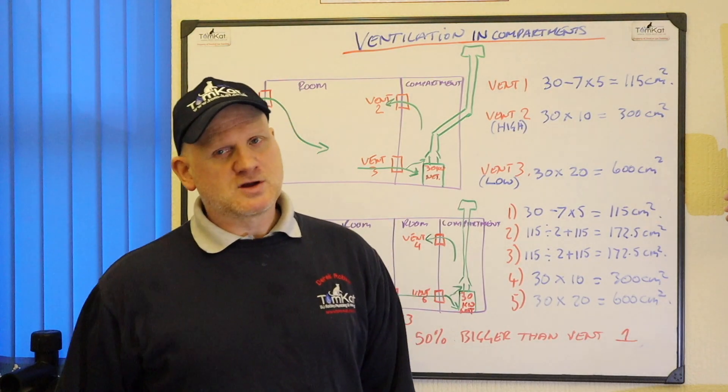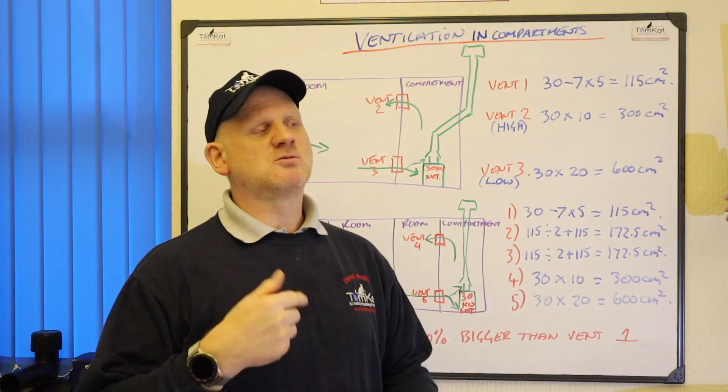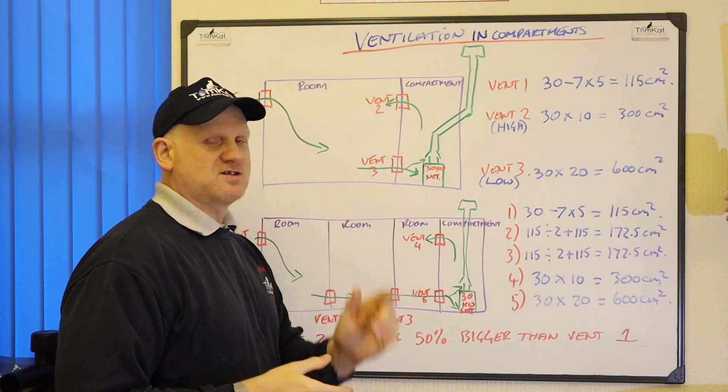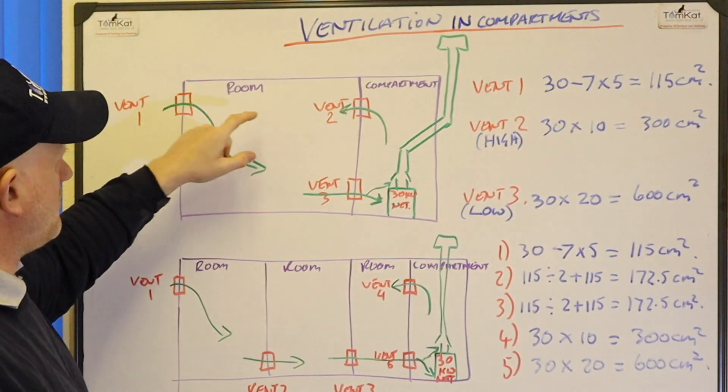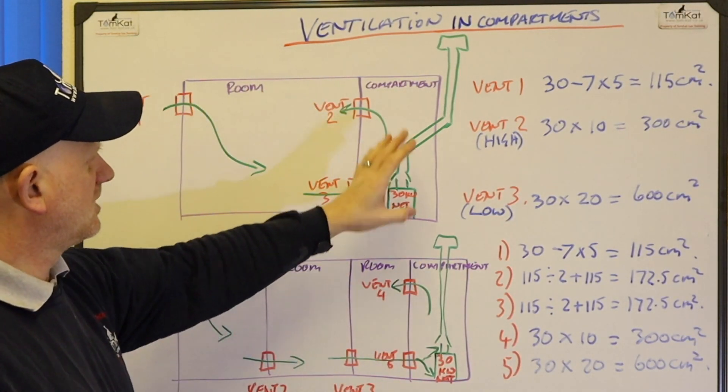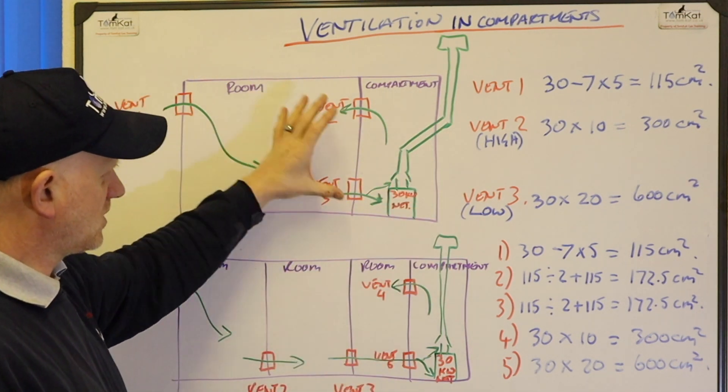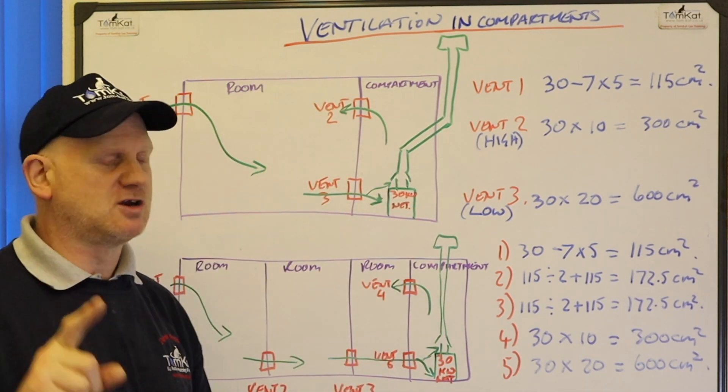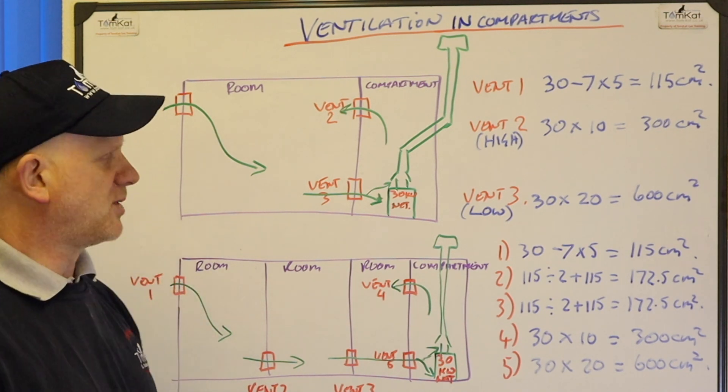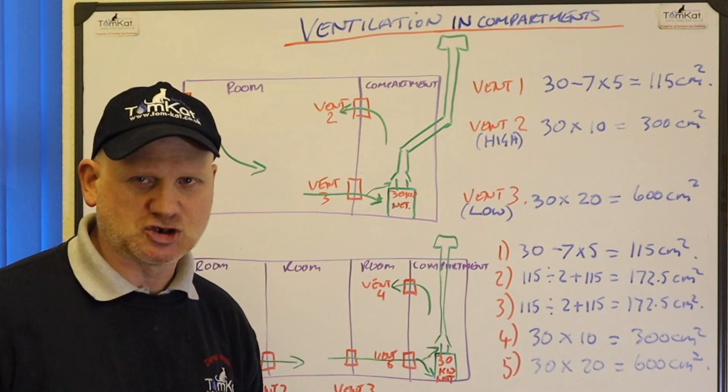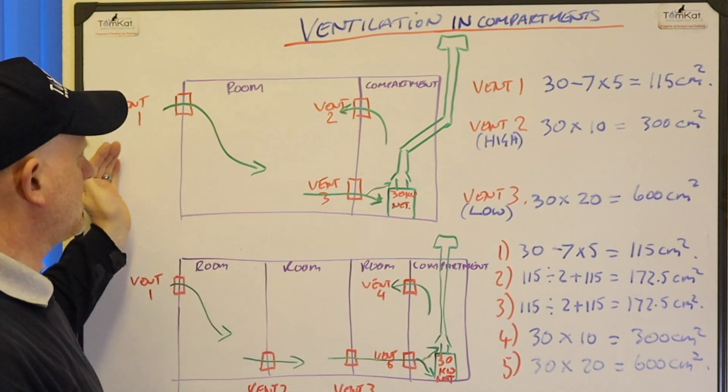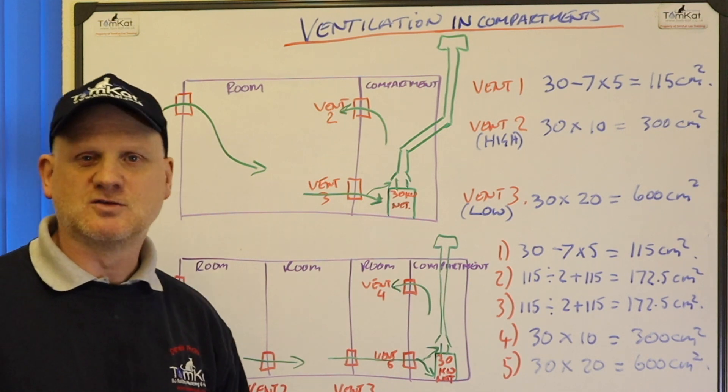So let's have a look at this compartment ventilation and we'll continue with open flue appliances. So we've got this scenario first, we've got a room and the compartment, we've got this open flue boiler installed in the compartment but we're taking our ventilation from the room. So because it's an open flue appliance it needs air for combustion, so we'll need a vent from outside to bring the fresh air into the room.